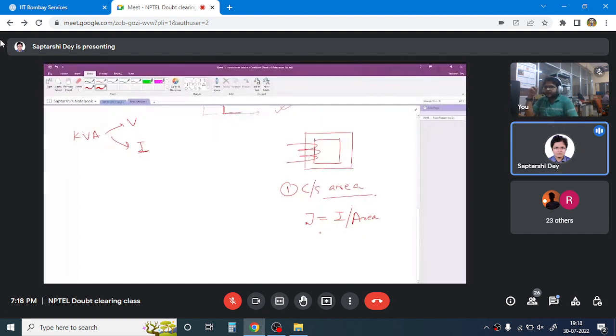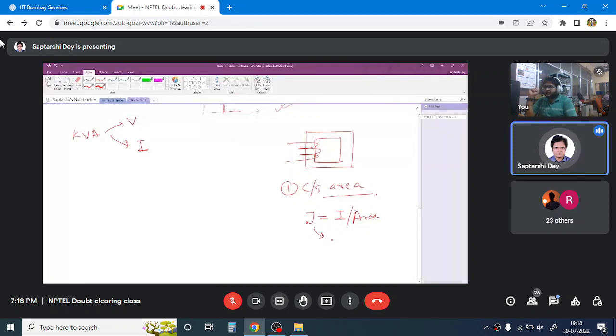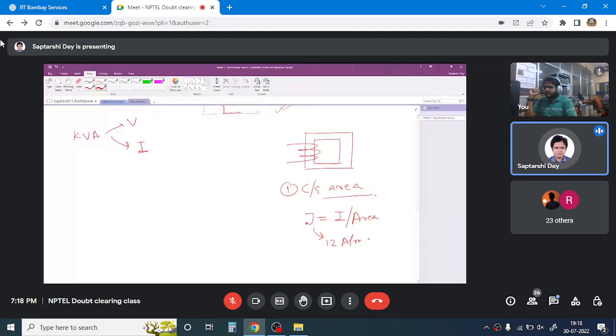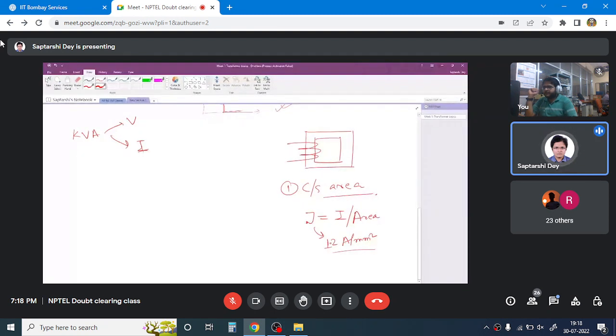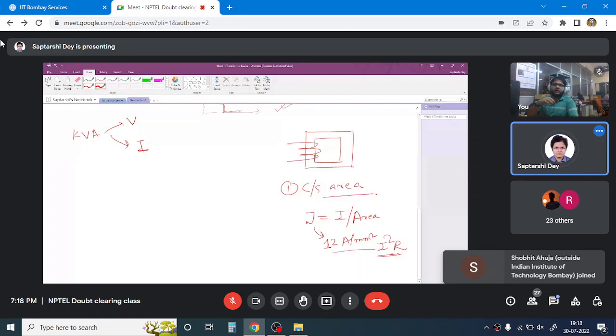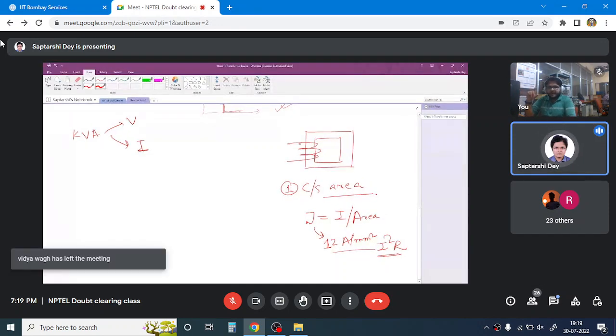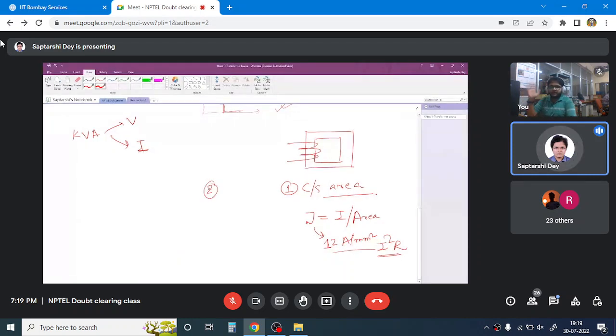This has a certain value. Say transformers are oil cooled, you can go to as high a value as 12 ampere per millimeter squared or something like that. 10 to 12, that can be done. If I exceed this value, or if the transformer is designed in such a fashion that at rated load current this current density value is exceeded, what will happen is there will be so much I squared R loss in the windings that the cooling system won't be able to dissipate it or remove the heat from the winding fast. As a result, the winding will burn down. Right, so whenever you are making a transformer, you are taking a certain gauge of wire for your winding, your current rating is fixed. Certain RMS value, beyond that you cannot push.